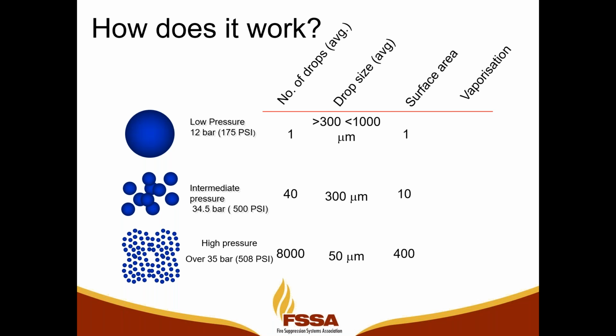When you're breaking them into smaller microns and a larger number of droplets per droplet of water, the benefit is that with each individual pressure of the different water mist systems, you're able to cover and expand your surface area coverage with those droplets. So, for example, with high pressure, you're increasing the surface area of that droplet's effectiveness basically 400 times.